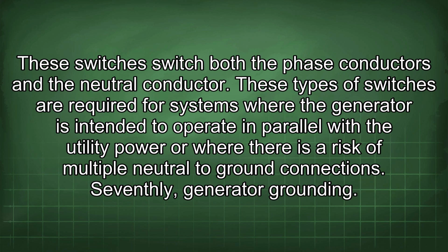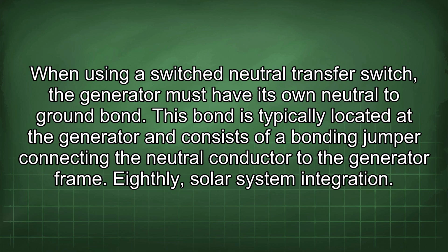These switches switch both the phase conductors and the neutral conductor. These types of switches are required for systems where the generator is intended to operate in parallel with the utility power or where there is a risk of multiple neutral to ground connections. Seventhly, generator grounding. When using a switched neutral transfer switch, the generator must have its own neutral to ground bond. This bond is typically located at the generator and consists of a bonding jumper connecting the neutral conductor to the generator frame. Eighthly, solar system integration.